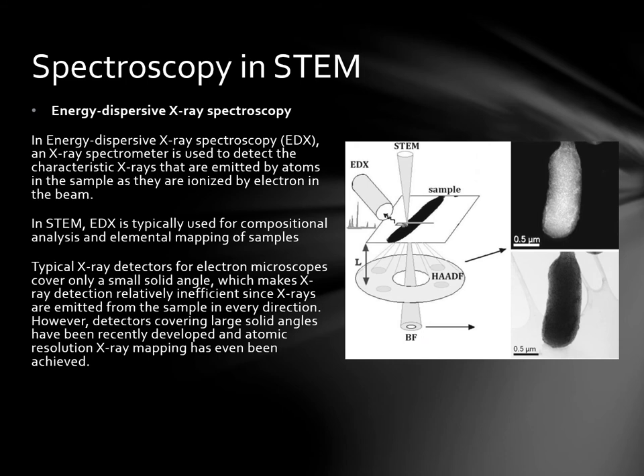Then we have energy dispersive x-ray spectroscopy. An x-ray spectrometer is used to detect the characteristic x-rays that are emitted by atoms in the sample as they are ionised by electrons in the beam. In STEM, EDX is typically used for compositional analysis and elemental mapping of samples. Typical x-ray detectors for electron microscopes cover only a small solid angle, which makes x-ray detection relatively inefficient since x-rays are emitted from the sample in every direction. However, detectors covering large solid angles have been recently developed and atomic resolution x-ray mapping has been achieved.